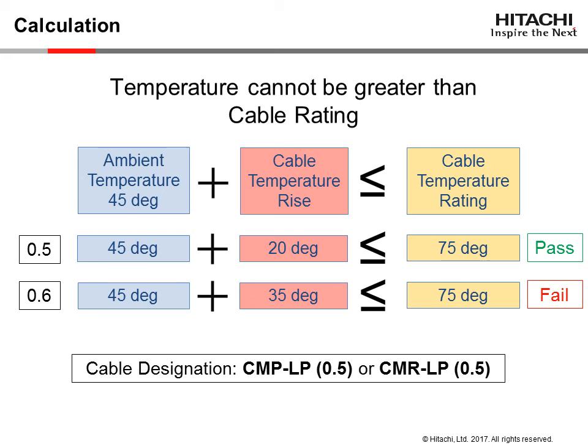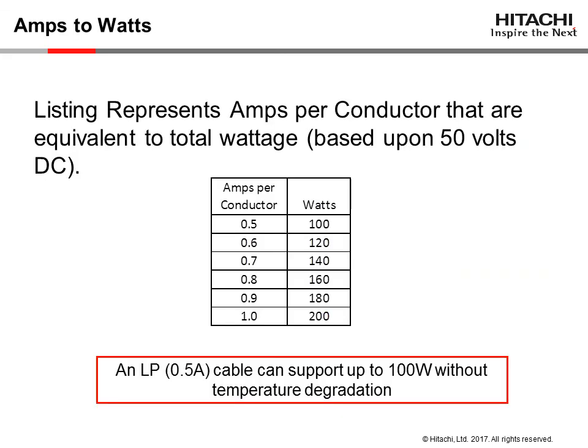As you can see from the chart, 0.5 amps per conductor at 50 volts is equal to 100 watts. Every 0.1 amp is equal to 20 watts. So the cable from the preceding slide with an LP 0.5 rating can support 100 watts of power without any degradation of the cable.